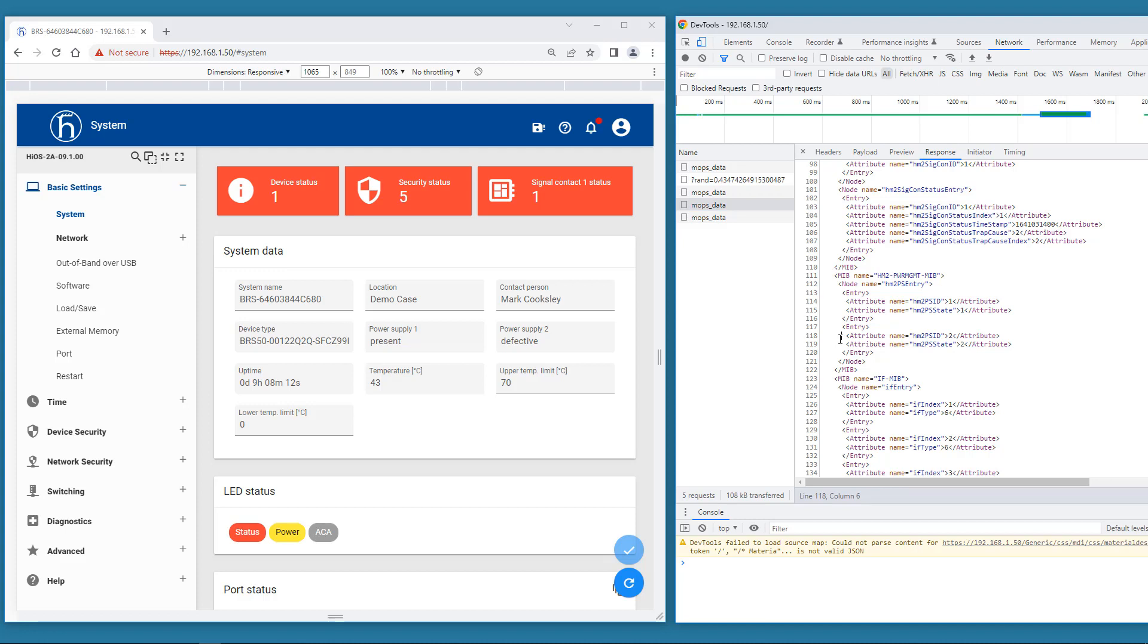As these statuses are numbers they normally require enumeration to obtain the plain text meaning. For the enumeration you need to look in the MIB. But in this case the meaning is already clear. Because we can see the same values in the GUI. 1 means present and 2 means defective.